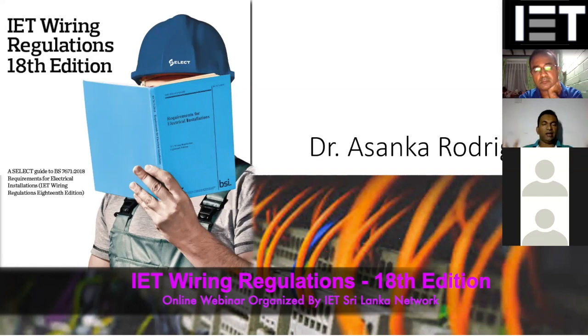So the potential rises simultaneously, and there will not be any difference between the potentials. Your equipment is damaged if there is a potential difference, and that potential difference is maintained at a safe value by the surge protective device. So by connecting equipotential bonding with the surge protective device, you will not get any problem of lightning damage.